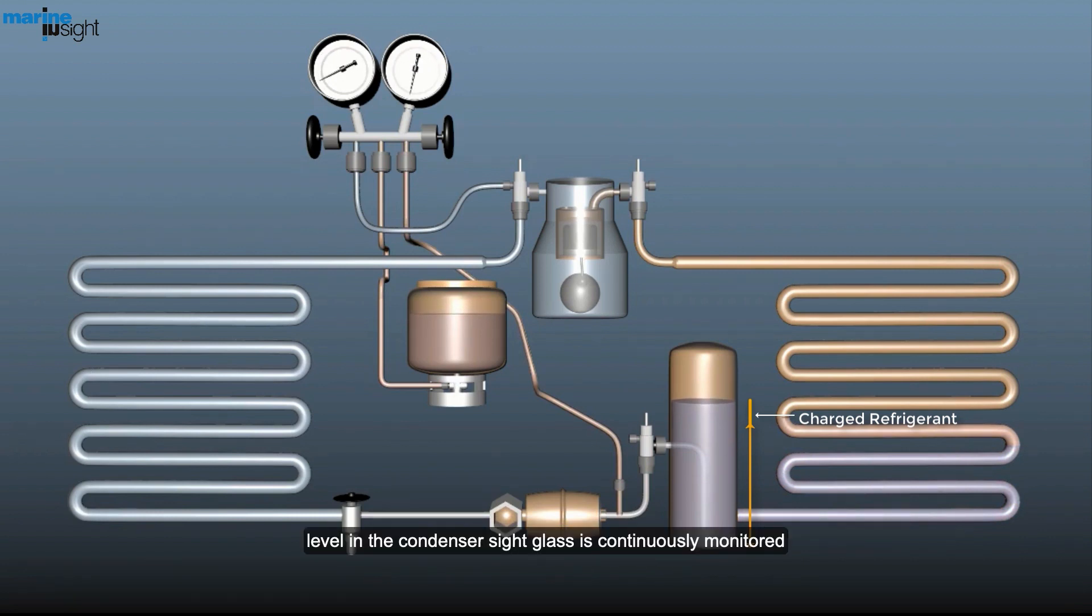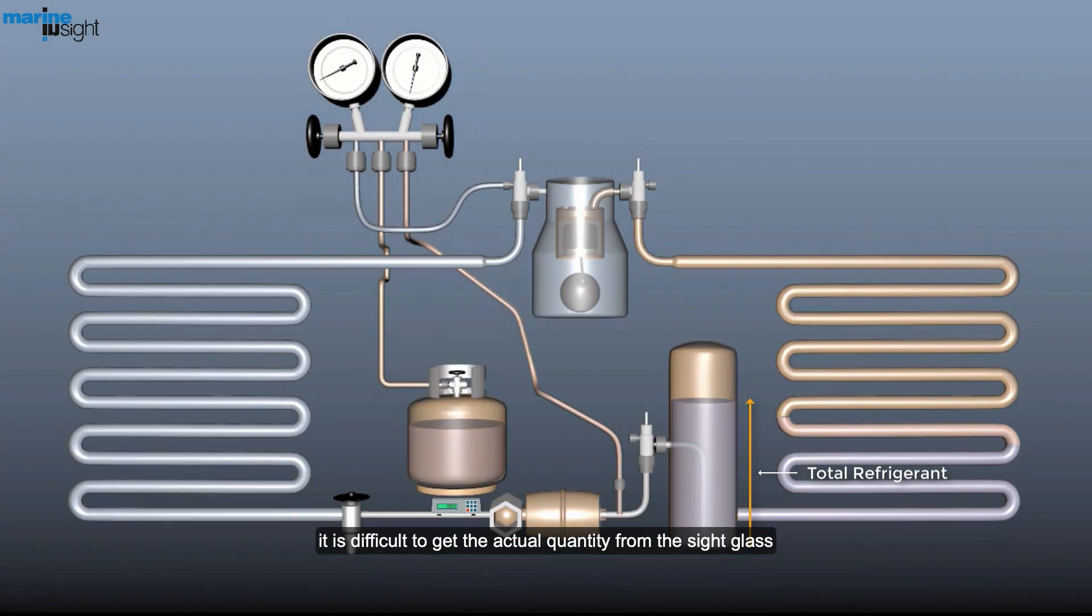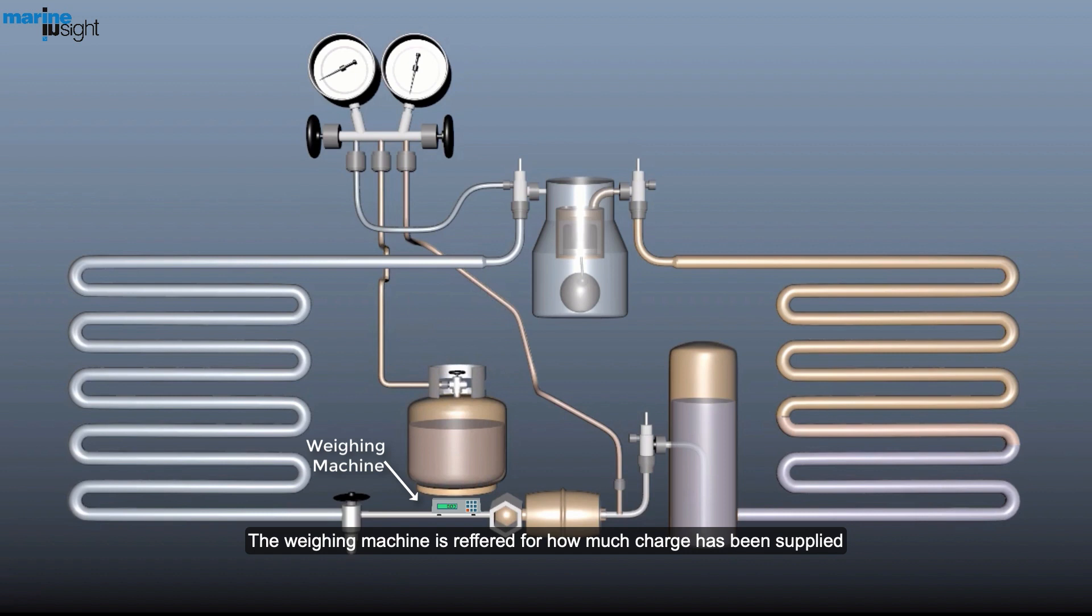The level in the condenser sight glass is continuously monitored. As the refrigerant is still circulating in the circuit, it is difficult to get the actual quantity from the sight glass. The weighing machine is referred to for how much charge has been supplied.